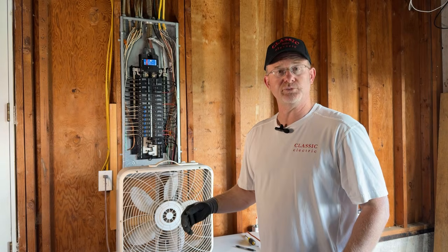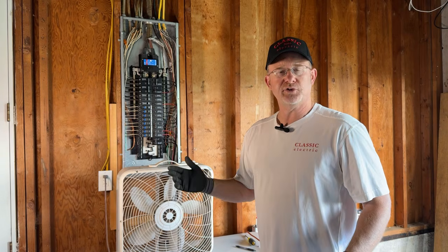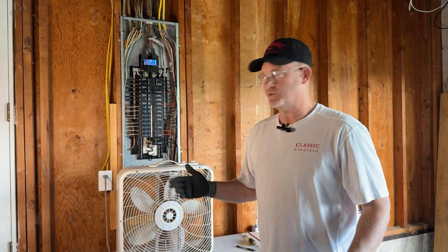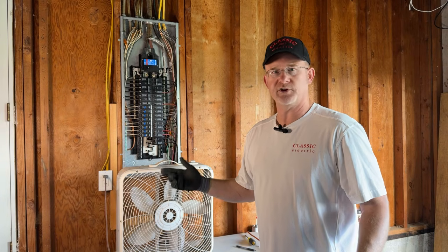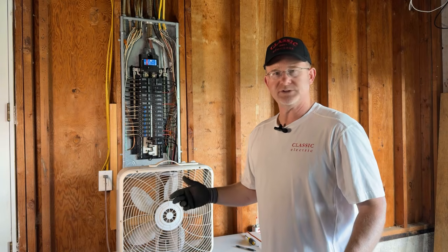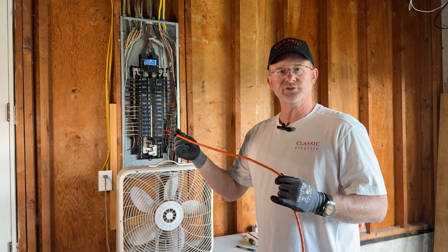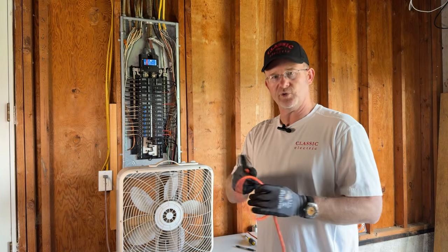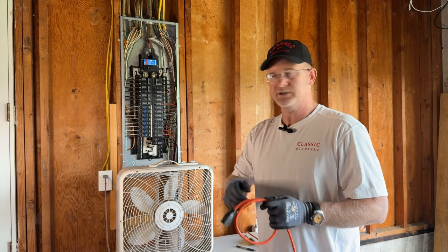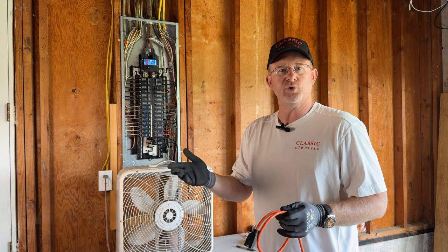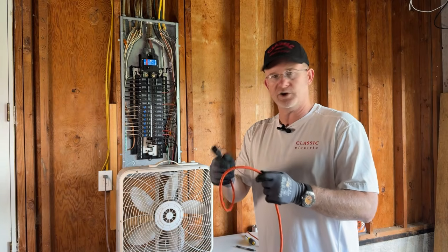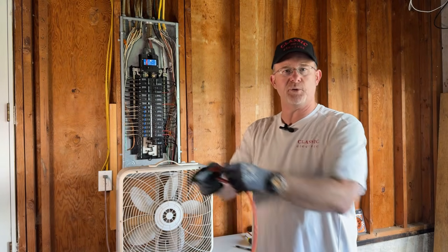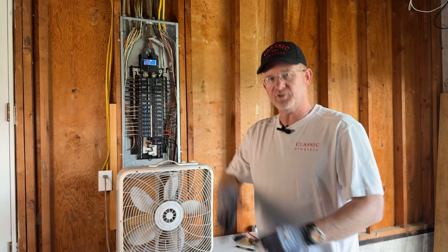Another example would be Christmas lights. Well, what happens at Christmas time? It's pouring down rain outside. So it's very common for somebody to tell me, hey, it's been dry the last few days and it's been working. And it starts raining again and then it trips. Well, what's happening? Well, the cord going out to the Christmas lights, either literally the cord or the actual Christmas lights themselves, if they're older, they've been out in the sun, they're breaking down, there could be a nick in the insulation. Hell, you roll them up and throw them in the box at the end of the year, and Christmas is over, and then you pull them back out.